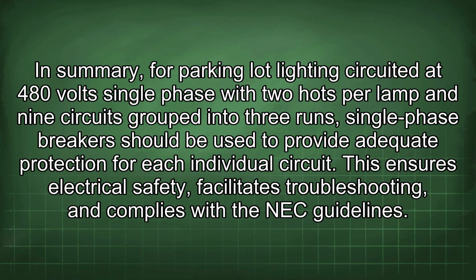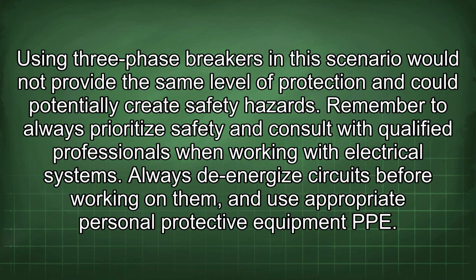In summary, for parking lot lighting circuited at 480 volts single-phase with 2 hots per lamp and 9 circuits grouped into 3 runs, single-phase breakers should be used to provide adequate protection for each individual circuit. This ensures electrical safety, facilitates troubleshooting, and complies with the NEC guidelines. Using three-phase breakers in this scenario would not provide the same level of protection and could potentially create safety hazards.